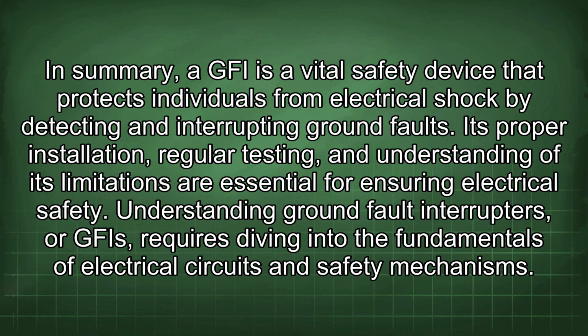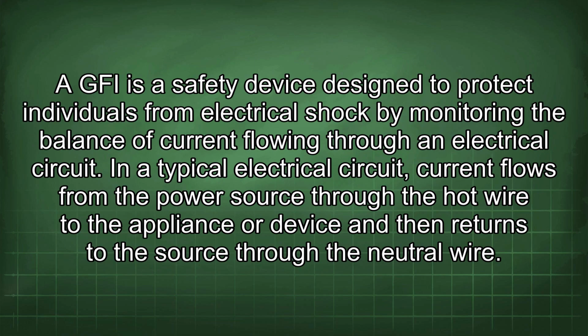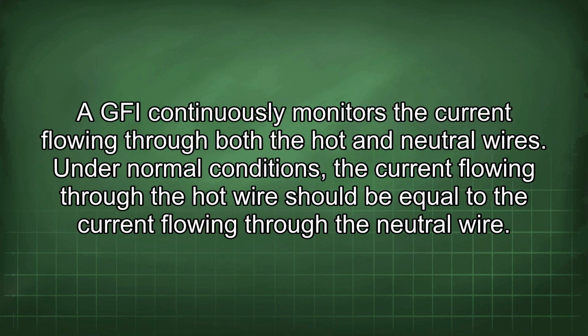Understanding ground fault interrupters, or GFIs, requires diving into the fundamentals of electrical circuits and safety mechanisms. A GFI is a safety device designed to protect individuals from electrical shock by monitoring the balance of current flowing through an electrical circuit. In a typical electrical circuit, current flows from the power source through the hot wire to the appliance or device and then returns to the source through the neutral wire. A GFI continuously monitors the current flowing through both the hot and neutral wires. Under normal conditions, the current flowing through the hot wire should be equal to the current flowing through the neutral wire.